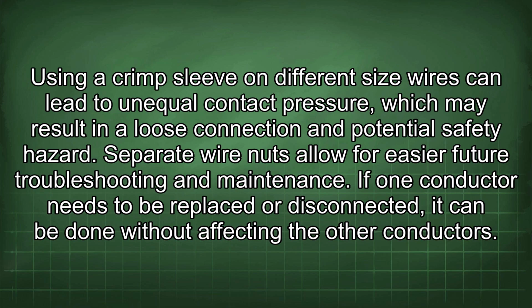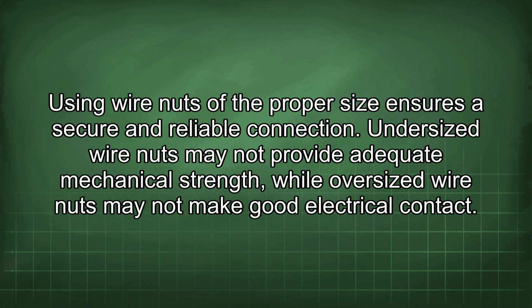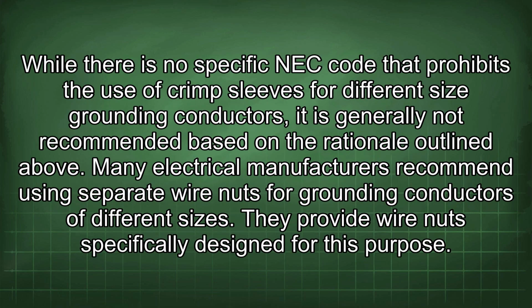Separate wire nuts allow for easier future troubleshooting and maintenance. If one conductor needs to be replaced or disconnected, it can be done without affecting the other conductors. Using wire nuts of the proper size ensures a secure and reliable connection. Undersized wire nuts may not provide adequate mechanical strength, while oversized wire nuts may not make good electrical contact. While there is no specific NEC code that prohibits the use of crimp sleeves for different size grounding conductors, it is generally not recommended based on the rationale outlined above.